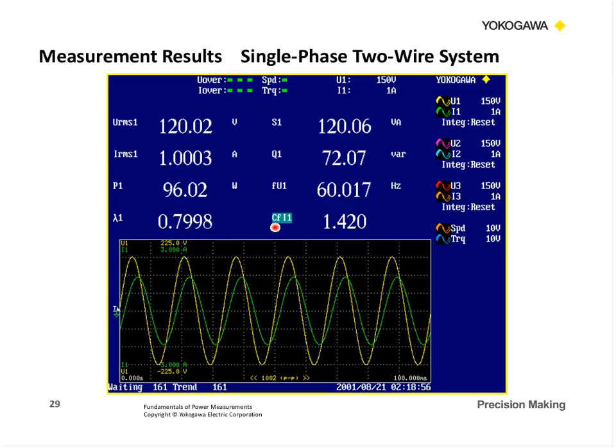I have one other function here highlighted, and that's crest factor. Now, crest factor is just a ratio of the peak value divided by the RMS value. So on a sine wave, that should be basically close to the square root of 2, and that's what we have here. That's what we've measured.